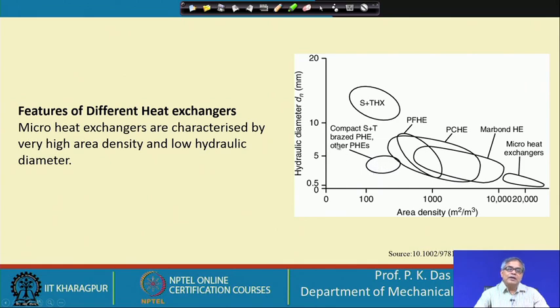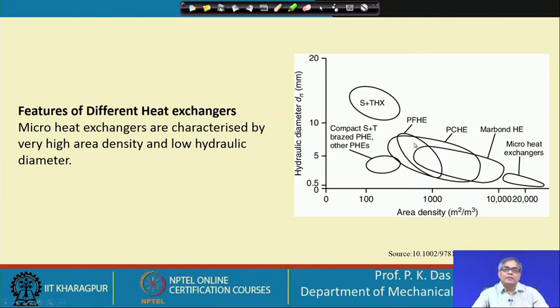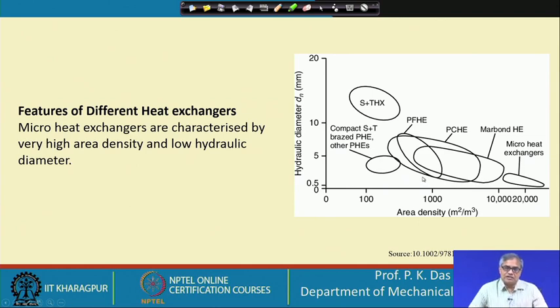Then we have compact shell and tube heat exchangers, plate heat exchangers, and brazed plate heat exchangers with smaller hydraulic diameters. There are overlapping regions where different kinds of heat exchangers appear. Plate fin heat exchangers represent increased compactness — for gas flow, if area density exceeds roughly 700 m² per m³, we call it a compact heat exchanger. Plate fin heat exchangers fall in this compact region, and printed circuit heat exchangers (PCHE) cover a large range, also within the compact heat exchanger domain.